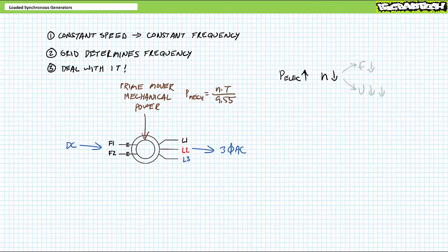Two things happen. First, obviously, frequency decreases since the rotor electromagnet isn't moving past the stator poles as quickly. Second, not as obviously, voltage magnitude also decreases because induction depends on the rate of change of magnetism. The rotor moving slower, the rate of change of magnetism is slower, thus the voltage magnitude induced at the stator windings is smaller.